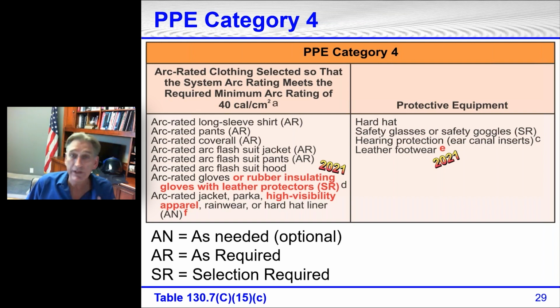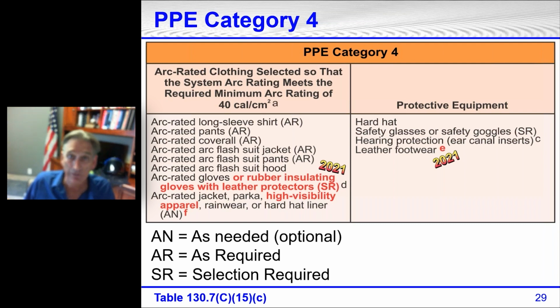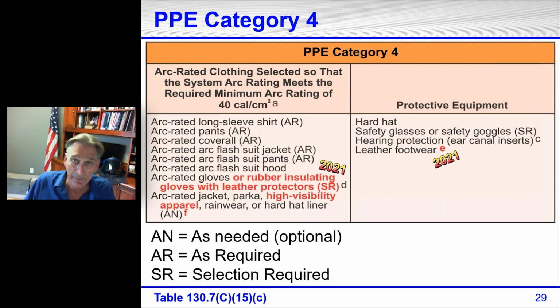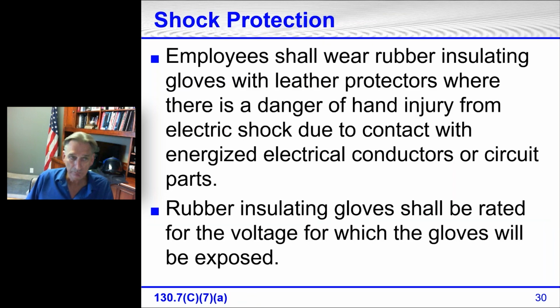Category 4, everything between 3 and 4 is exactly the same. The only difference is Category 3 turns to Category 4, and the 25 calories per square centimeter changed to 40 calories. So the minimum arc rating for a Category 4 has to be at least 40 cal. All right, so shock protection. I know so far we've talked about arc flash or arc-rated PPE. We'll talk about shock a little bit.